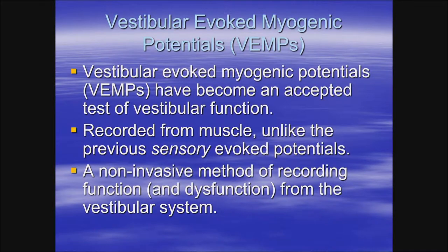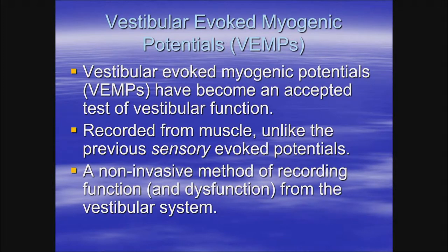Since the 1990s, we have at our disposal a way to easily evoke a vestibular response using sound stimulation. We can also use bone-conducted vibration, but my emphasis in this talk is with air-conducted sound with headphones. If you have a brainstem auditory evoked potential system in your laboratory, you can do VEMPs — it's just a question of changing the stimulus characteristics.